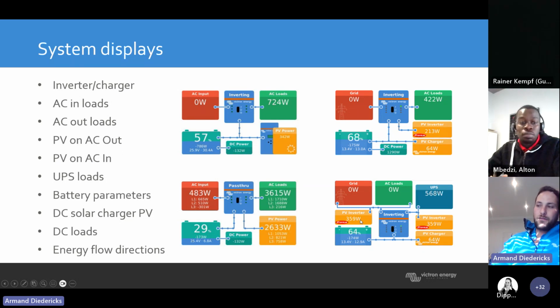So yeah, if you've got a high inverter, say for instance, you've got a 3-phase 10 kVA system, but you've got a 27 kilowatt connected onto the output, and you've got a 27 kilowatt connected to the input. Both can work. The only disadvantage: once Eskom goes down or the power utility goes down, this grid-tie system will switch off. But yeah, this is how it looks when you've got an energy meter installed. So you've got the grid, the AC loads, which is non-dedicated loads, and then your backup. So if Eskom goes down or utility goes down, the AC load will automatically go to 0, and then the grid goes to 0. If you want an AC load, which is a non-dedicated load, connected to the output 2, you can actually program a general flag and multiple other settings. If the SOC reaches 70%, close the contact and provide power to the non-dedicated loads, such as air cons, geysers, etc. Right.